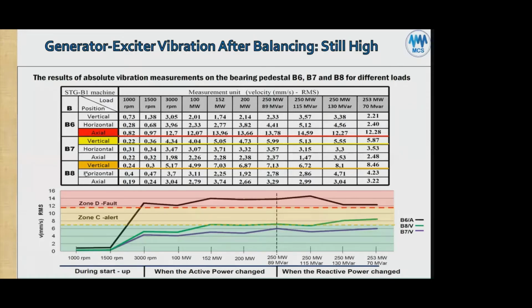Okay. So we have a vertical vibration. B8 is still having a high vertical vibration of roughly 8.46 millimeters per second, and we have a vibration of 5.87. And this is after it was smoothly balanced, by the way. And how do we know it was smoothly balanced? We go back to the first. We reached 3,000 RPM and we only had, well, not so smoothly because it has some other problems, doesn't it? It's at 4.34 in the vertical direction and 5.17. And then we ended up with 8.46 after full thermal loading and loading from the power generation.